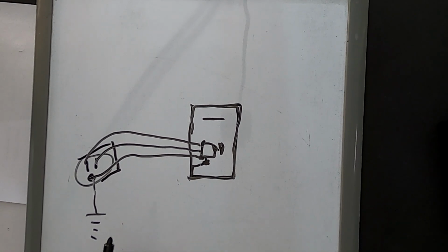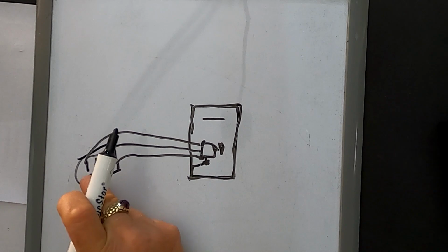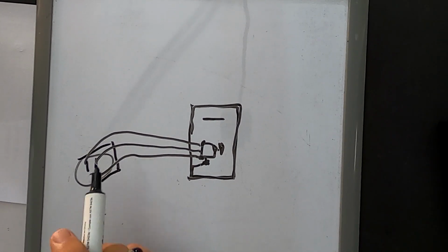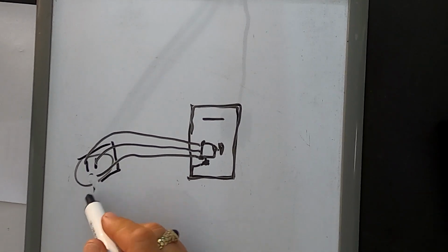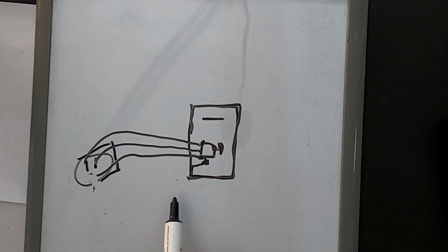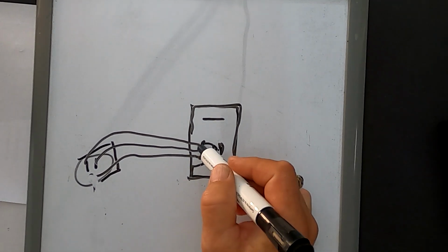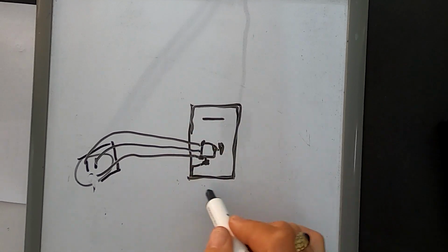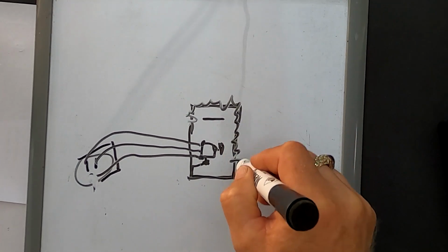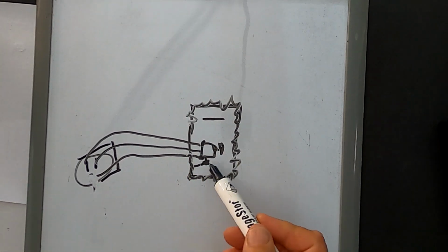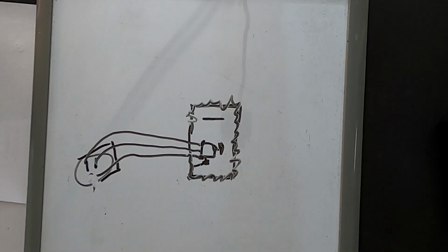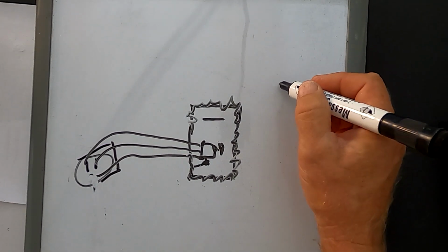But now somebody comes along and thinks, well, I don't need that ground prong, so they cut it off, you no longer have a path here, because this is plugged into an outlet that's properly grounded. So now what happens if this situation happens where one of the hot wires comes in contact with the metal around this table saw or the motor frame? Now, this whole table saw becomes energized. Nowhere to go. It's looking for a path to ground, but somebody cut that off. Not there. So what happens?